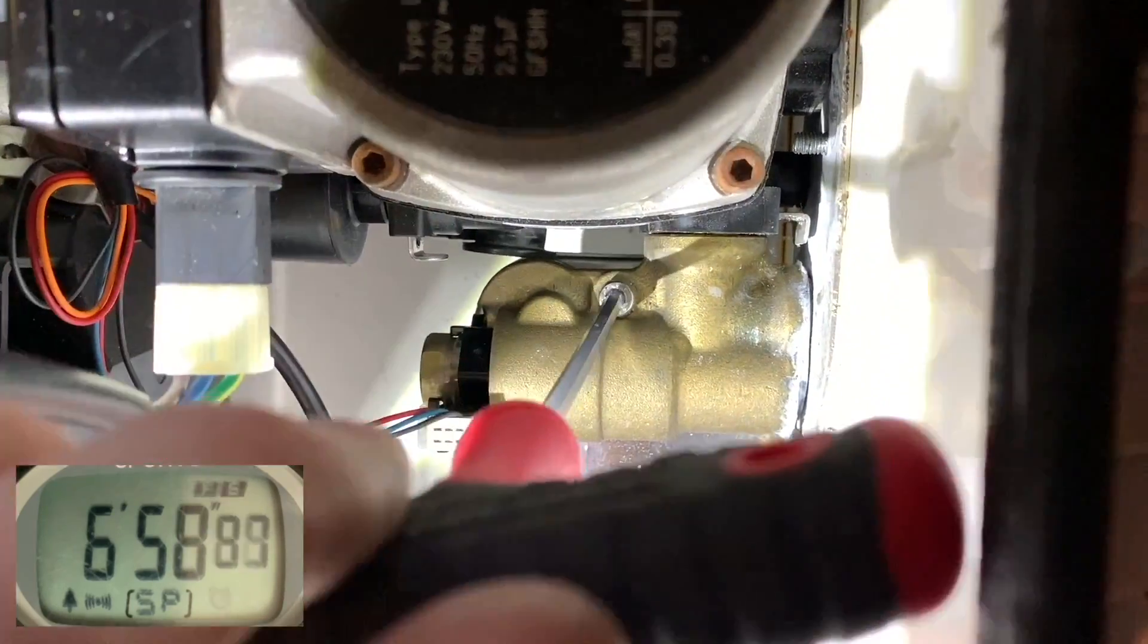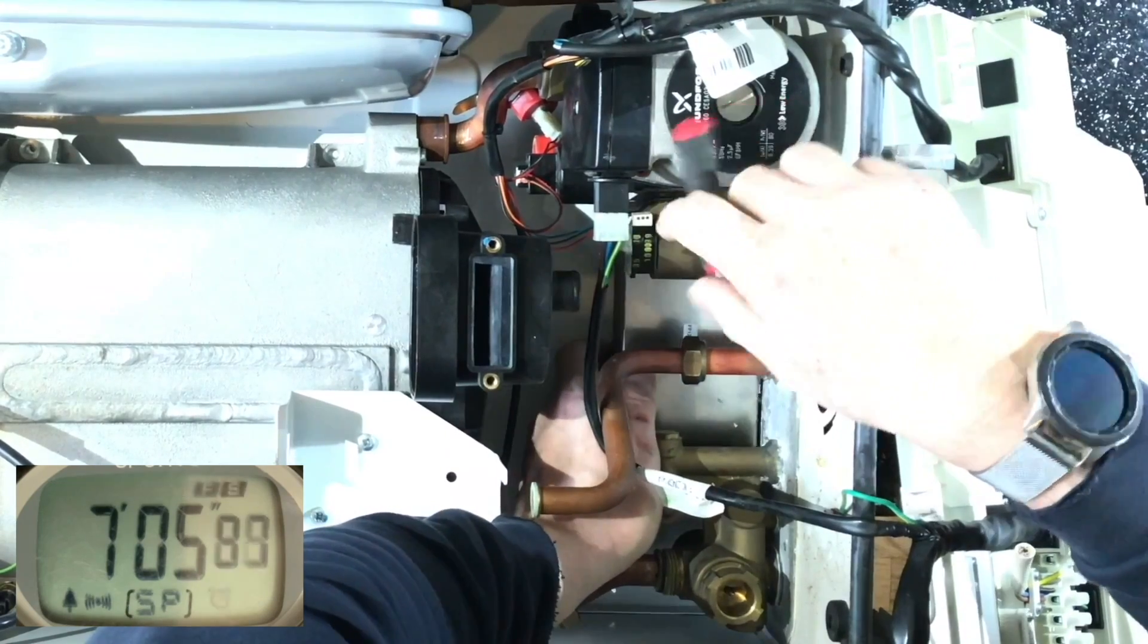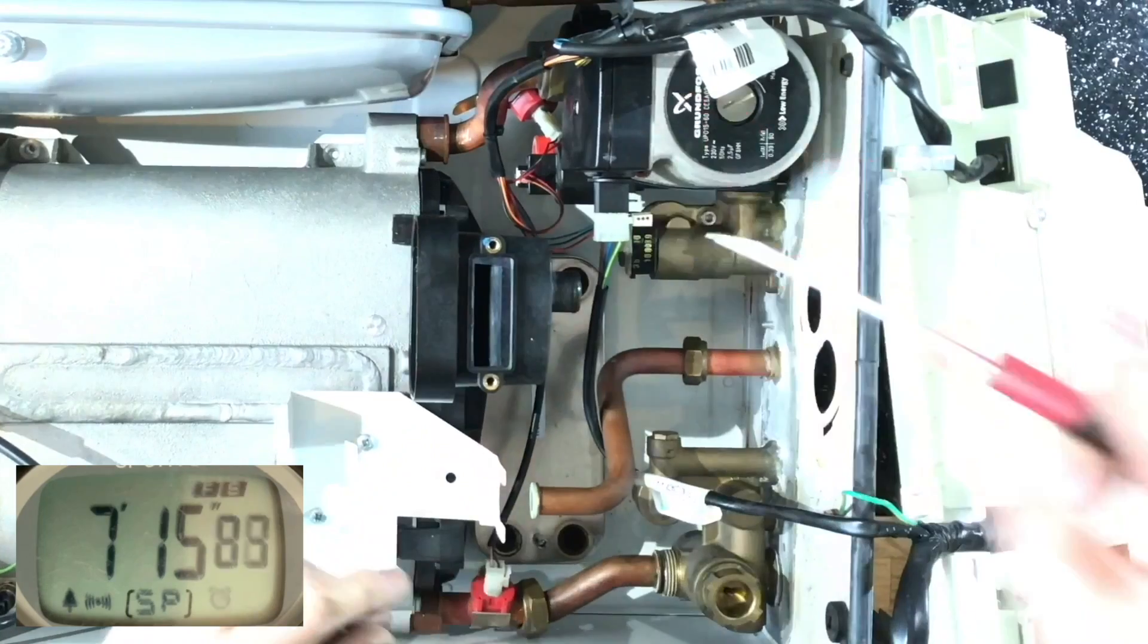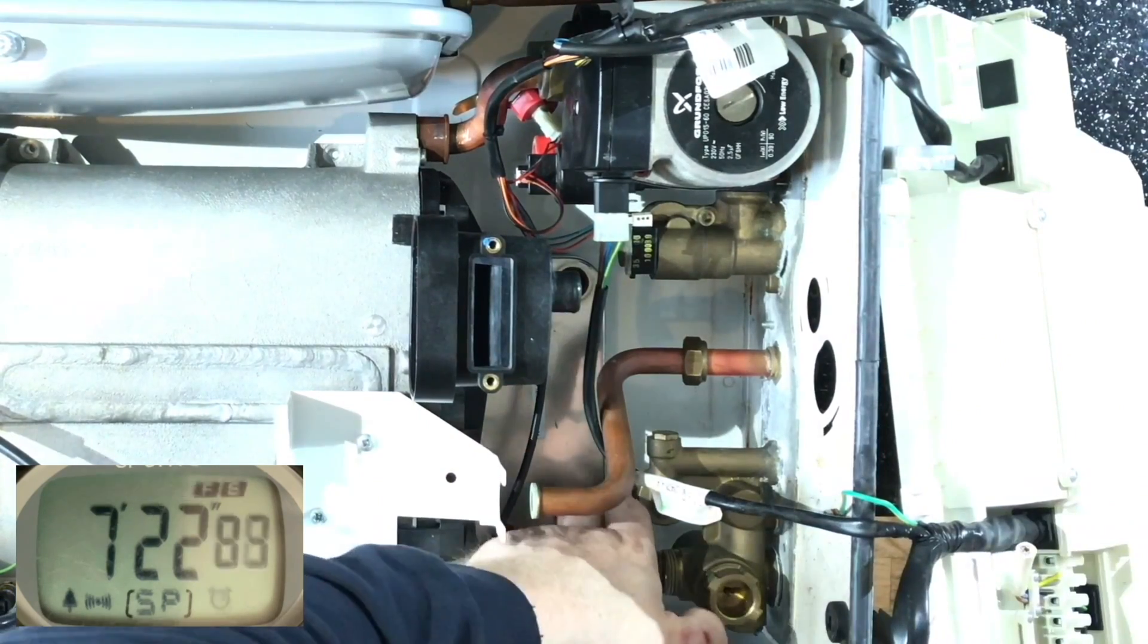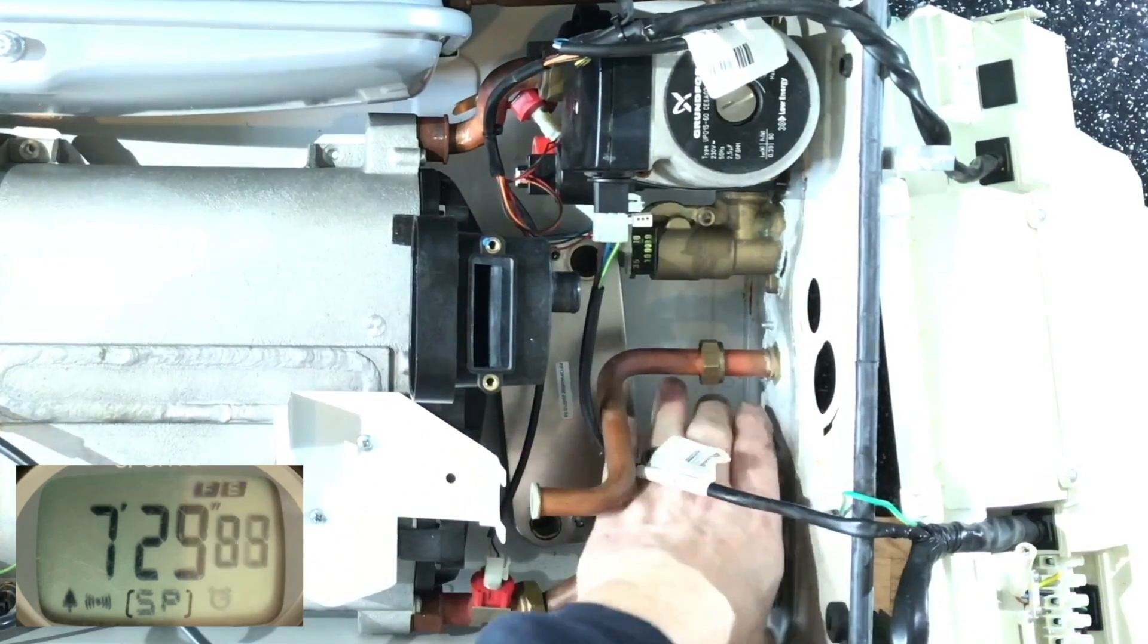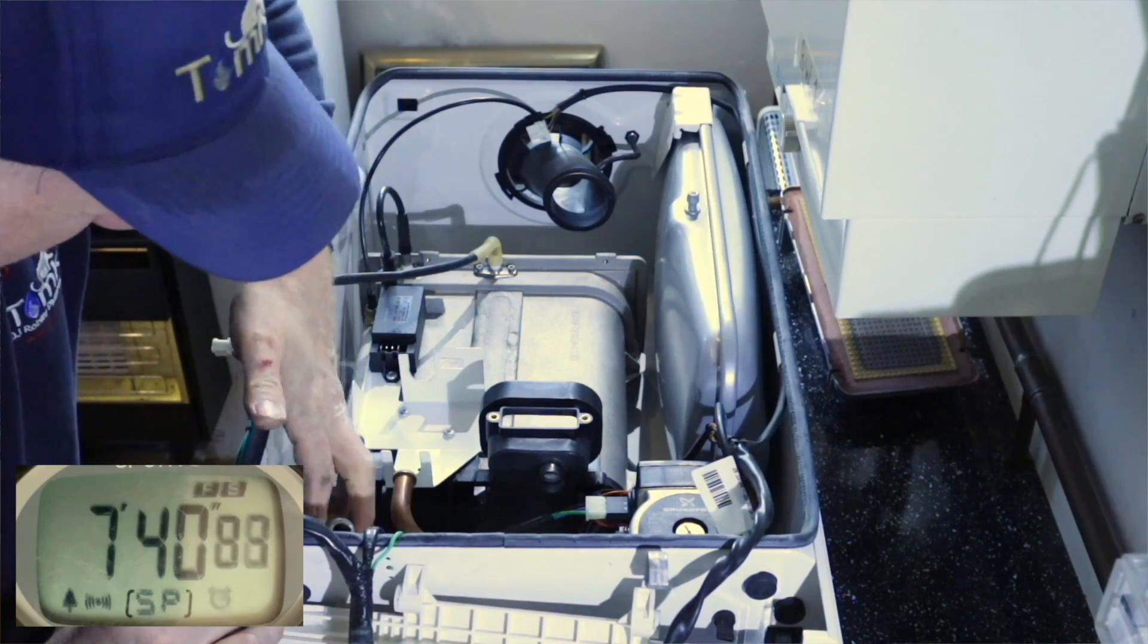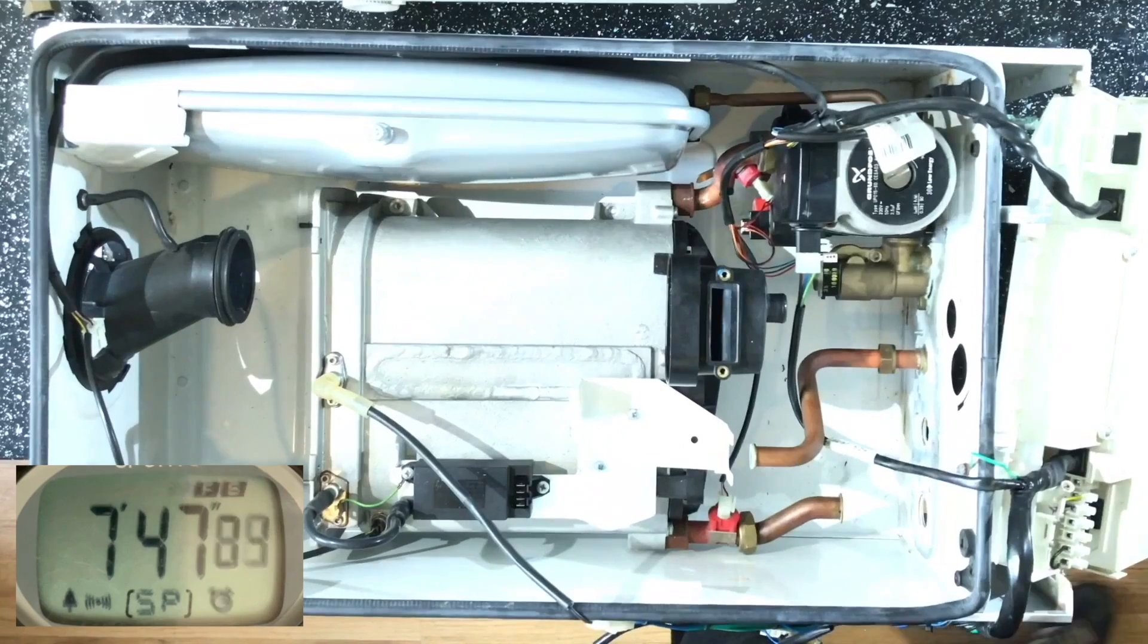Now this plate-to-plate heat exchanger is dead easy to remove. It's just literally these two Allen screws, 4mm Allen screws, dead easy to remove. So I'm just going to drop this down at the bottom of the boiler case, and then I'm going to remove this left-hand side hydro block, so then I can take the plate-to-plate out easier.